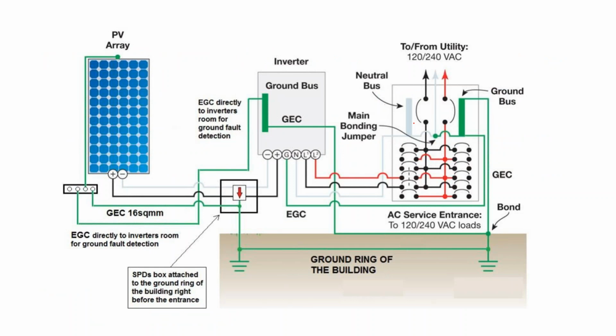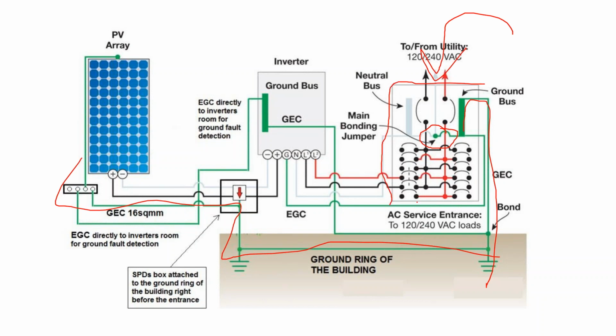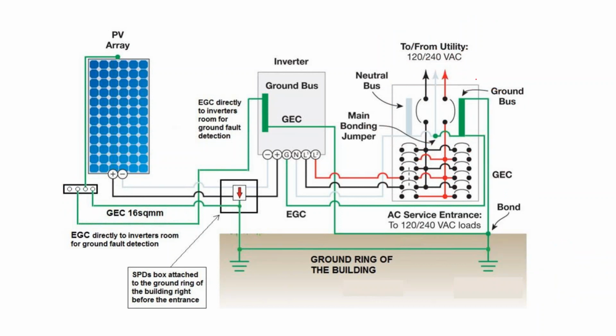This graphic should be a lot more clear now in terms of what's happening at this point. So we have our grounded system, and then we have our utility service entrance, and in this case, our meter is being combined with our service panel. Sometimes you might have a disconnect switch right here, and you'd have the bonding occur in the disconnect switch. Or you might have a standalone meter case, and this bonded connection occurs in that meter case. Well, that's not what's happening here. Right here we have what's called a meter-base combo, where it's a combination load center and meter base. The meter is built into the load center, and we see a call out for bonding the neutral to ground inside this case.